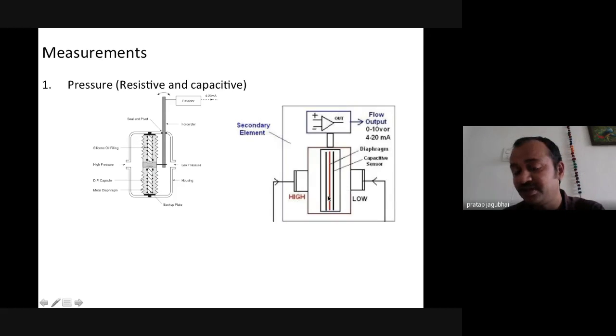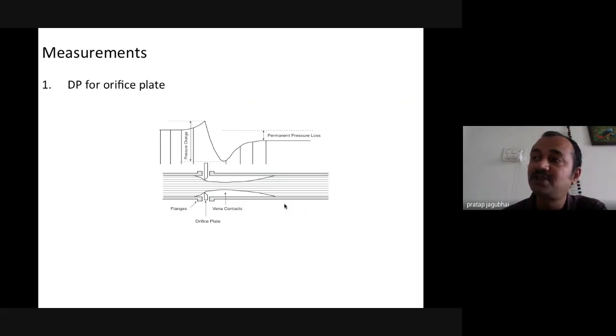Similarly, for the differential pressure, you will have a high pressure and a low pressure at the one end. Then the differential pressure can be sensed with the help of displacement change, which is happening inside the capacitance, the plate of the capacitance. So this plate movement is varying the capacitance. So capacitance C equal to epsilon A by D. So the area is proportional to the capacitance change, which will be detected in the form of the differential pressure transmitter, which is very widely used to measure the differential pressure, to measure with the orifice type of meter.